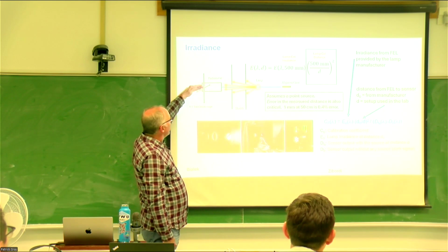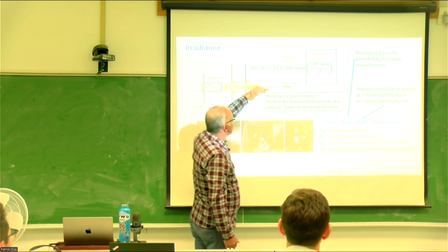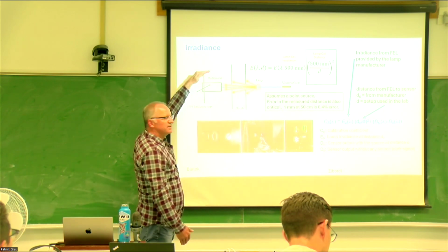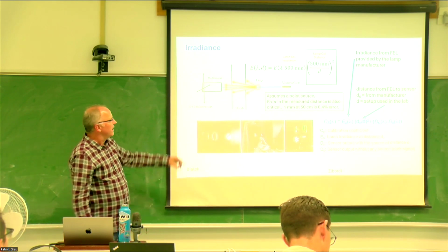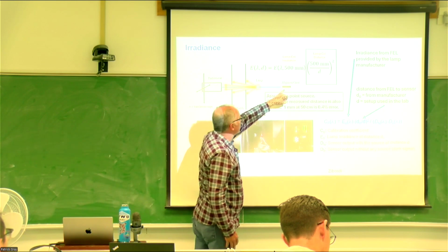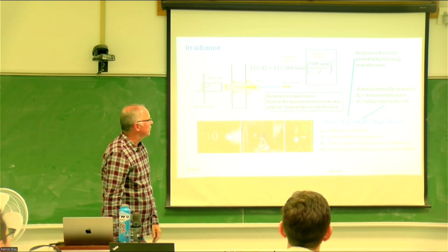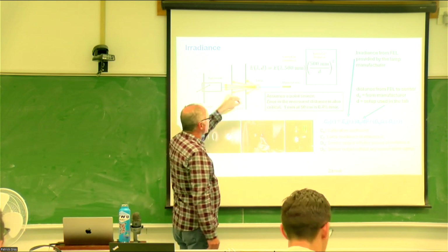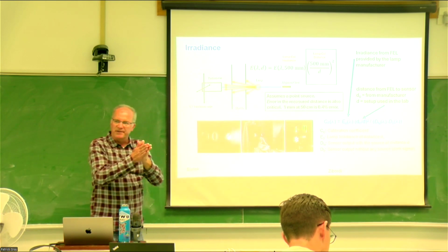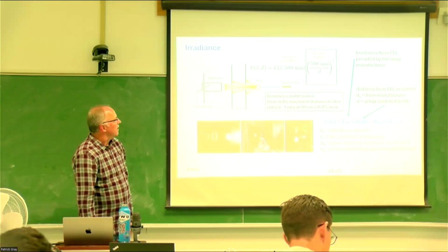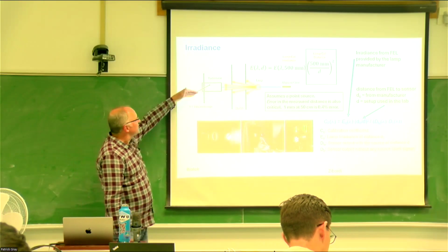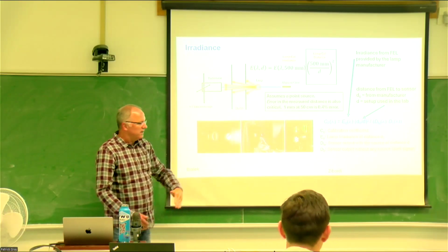And so then that is mounted, and you want to make sure they're all on the same relative plane, in this axis and the up and down vertical axis, as well as making sure this is directly in alignment with the lamp. So we take the alignment laser and shine it right next to the center of the filament, and make sure it's all aligned well. There's a translation stage you can add in here.